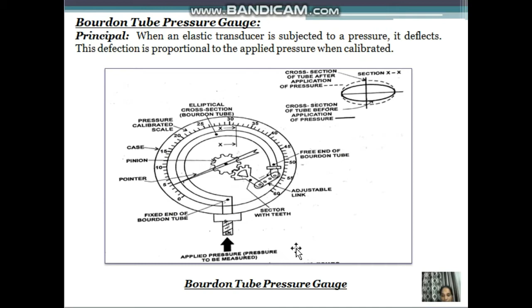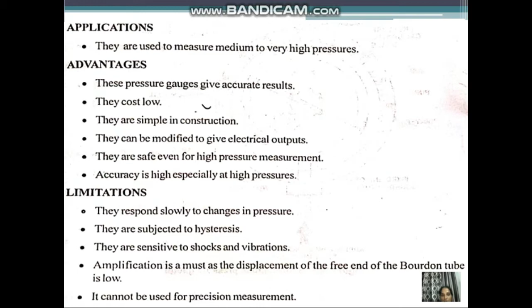Coming to the applications, Bourdon tubes are used to measure medium to very high pressures. Coming to the advantages, the cost is very low, the results are accurate, the construction is simple, and it is safe even for high pressure measurement, and very accurate especially at high pressures. But in spite of all these advantages, we have limitations also. They respond slowly to change in pressure, and they are subjected to hysteresis. They cannot be used for precision measurement, as the displacement of the free end of the Bourdon tube is low, and they are sensitive to shocks and vibrations also. So these are the applications, advantages, and limitations of the Bourdon tube.